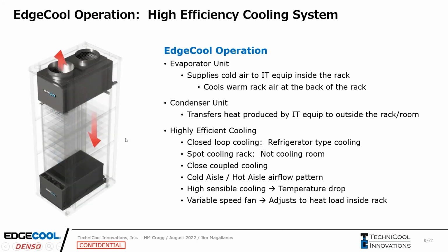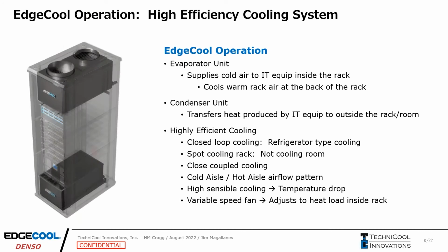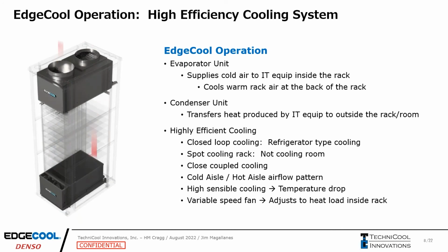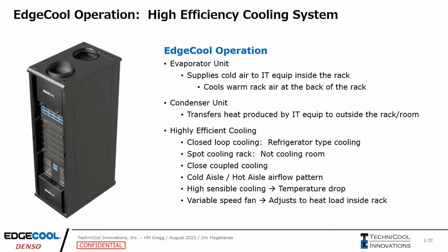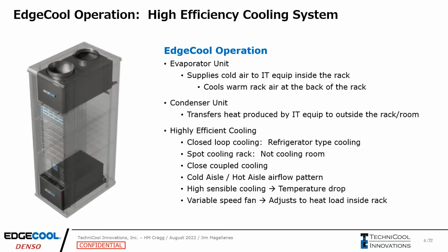And so why does this make it highly efficient? One, it's a closed loop cooling system. You can think of your refrigerator, thinking of shutting the door to your refrigerator and keeping that cold air just circulated inside the rack. You're not introducing any type of outside heat to that space to be cooled. Next is we're spot cooling the rack and not cooling down the room. So that's really efficient. We're targeting our cooling within that rack only.